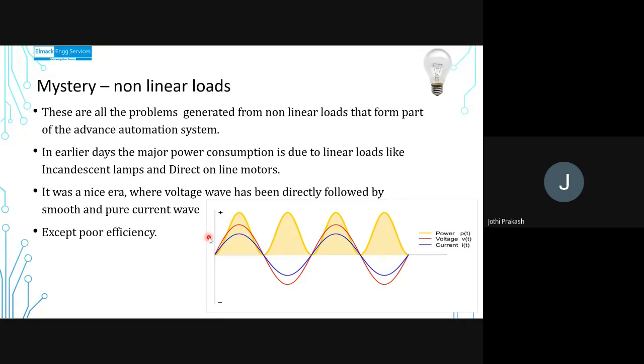We know that in earlier days, before 1990, the major power consumption was due to linear loads like incandescent lamps and direct online motors. It was actually a nice era for electrical people. There wasn't much of a problem except efficiency. And here is a screenshot of a waveform. The red indicates the voltage, the blue indicates the current waveform, and the yellow waveform indicates the power graph, where the current waveform follows the voltage, being a linear load.